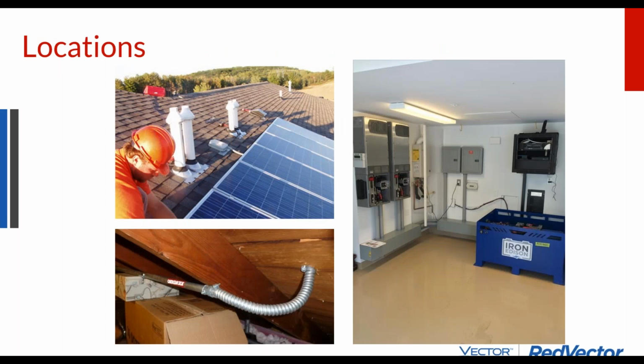Locations. This comes into play a lot in the solar industry because we install on the rooftop, which is not just a wet location, it's also a hot location. And so the boxes that you buy, your terminals that you buy in the solar industry are rated for a hotter environmental rating than the standard stuff you get at the store. And so if you're doing all your temperature calculations at the hotter temperature rating, and then you're running out to Home Depot and you're buying the stuff at the lower temperature rating, you can run into a design error that way. So generally, the equipment that you're using on the rooftop is going to be specialty equipment.